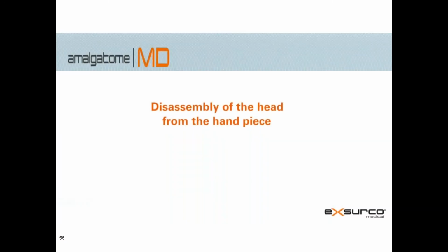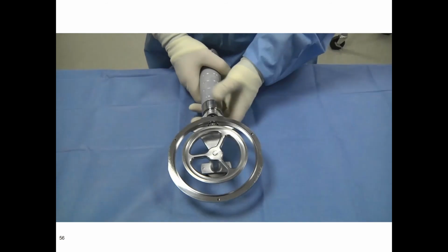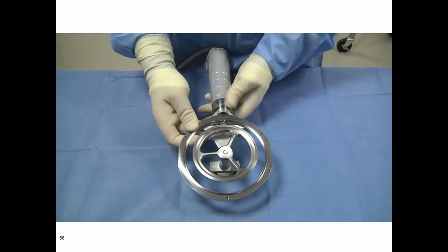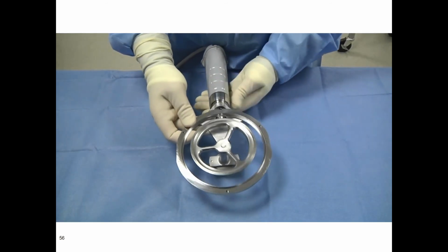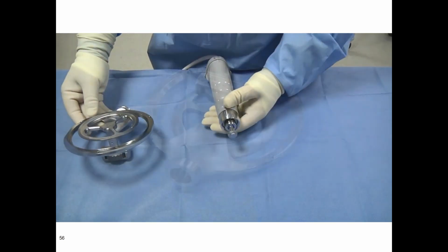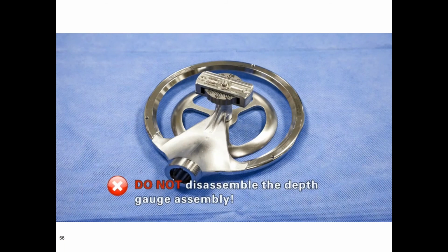Disassembly of the head from the handpiece. Turn the device lever side down. Turn the locking knob to loosen and remove the housing from the handpiece. Do not disassemble the depth gauge assembly. The head assembly, excluding the blade locking ring, has been validated for sterilization and will require factory recalibration if disassembled.